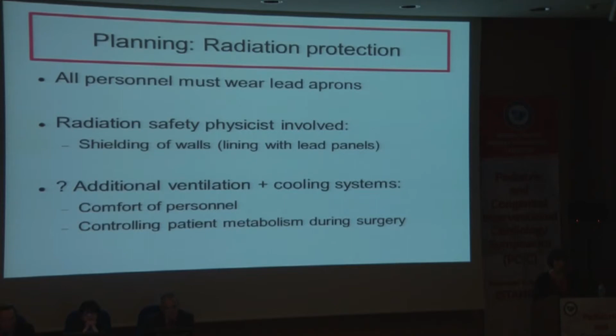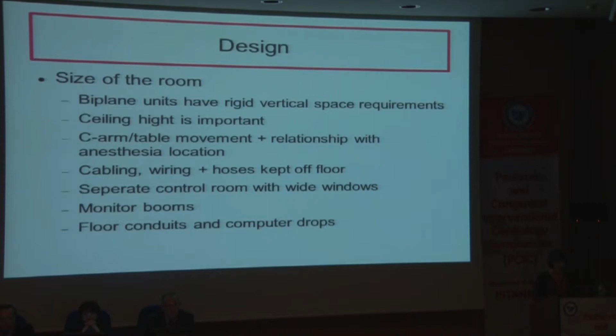The next thing that is important in the design is obviously the size of the room, and the thing is that biplane units have rigid vertical space requirements, and the ceiling height is quite important. If you look at the C-arm or the table movement, it is important to have enough space in relationship with anesthesia location. Obviously, care should be taken with the cabling, wiring, and hoses to be kept off the floor. There should be a separate control room with wide windows, as we have in the cath lab. You have to have your monitor booms and floor conduits and computer drops. It's quite obvious, but it has to be thought of.